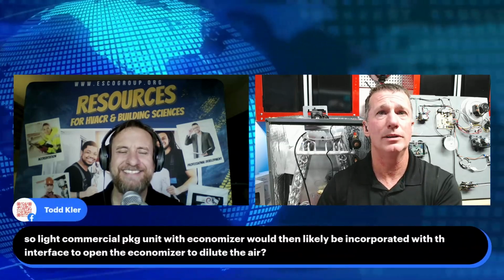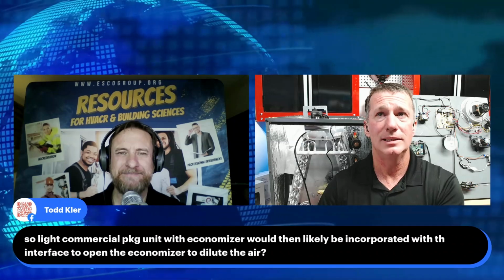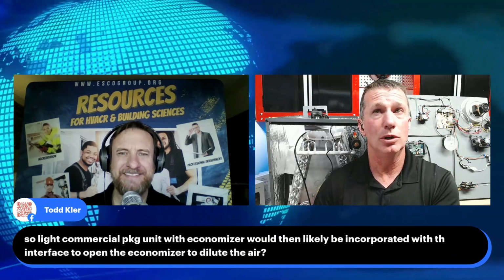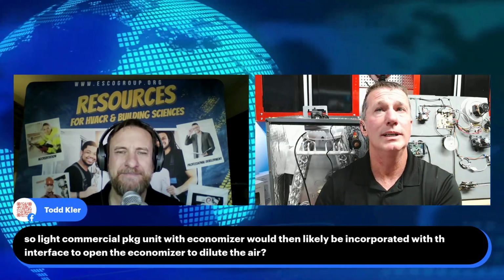One of the questions that came in from Todd Clearer: if it was on a light commercial package unit that was required to be tied into an economizer, could we do that? Absolutely. We got a set of dry contacts. We could also bring that into any type of signaling device that we needed, particularly if our local codes required it for things like hospice care facilities where we would want it tied into some type of an alarm. So they do have dry contacts to use for that.